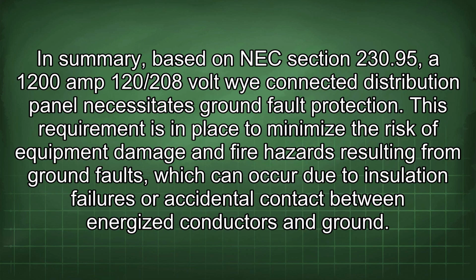In summary, based on NEC Section 230.95, a 1200 amp 120/208 volt Y-connected distribution panel necessitates ground fault protection. This requirement is in place to minimize the risk of equipment damage and fire hazards resulting from ground faults, which can occur due to insulation failures or accidental contact between energized conductors and ground.